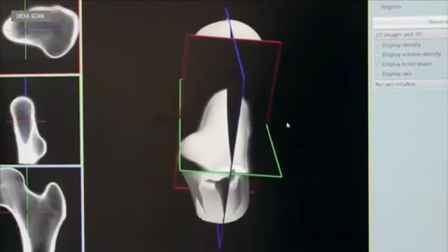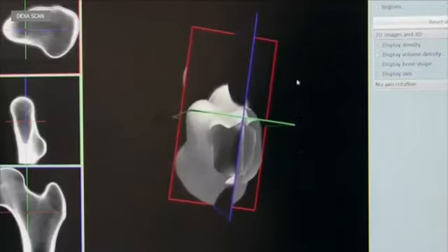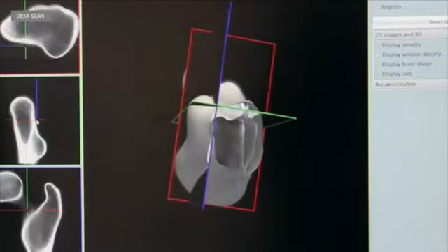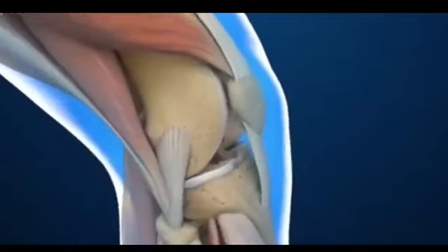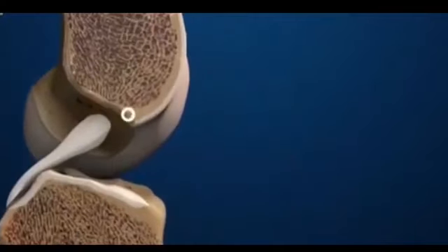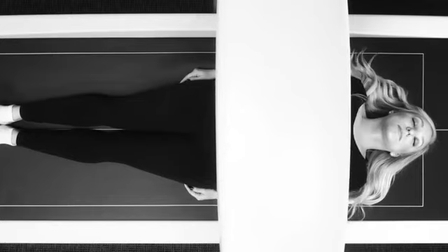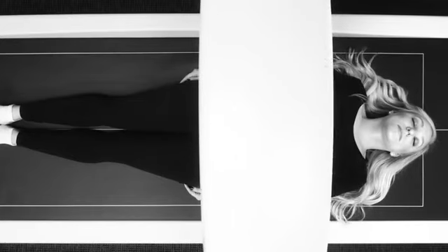The physics of dual energy, as opposed to single-energy photon sources, in principle is where two different energy sources, 30 to 50 kiloelectron volts and 70 kiloelectron volts, allow greater discrimination of soft tissue and enhanced bone edge detection, and was a major advancement in the accuracy as well as precision of dual-energy X-ray absorptiometry, or DEXA.